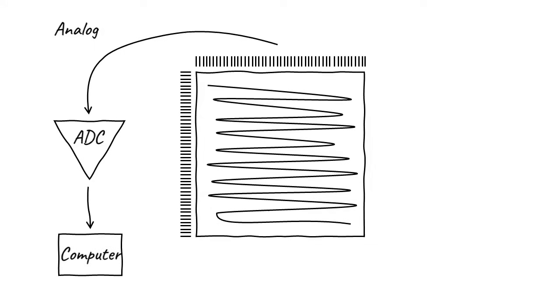At this point, the pixel values represent the total integrated intensity in each frame. If you perform dark and gain correction on these values within a computer, you end up with integrating or linear mode frames.